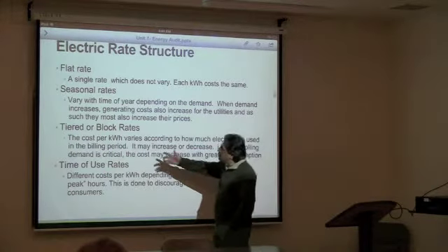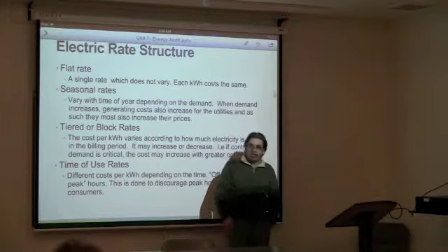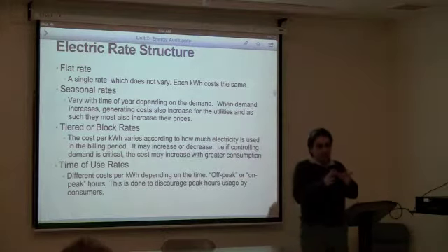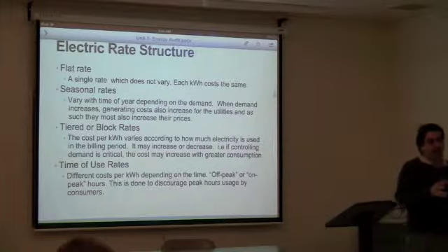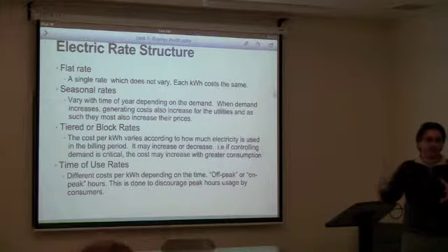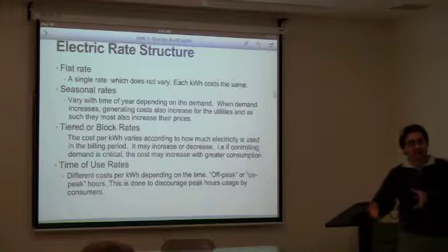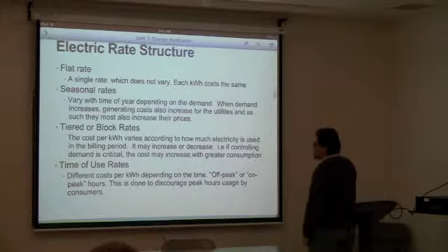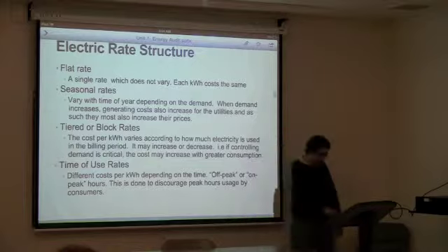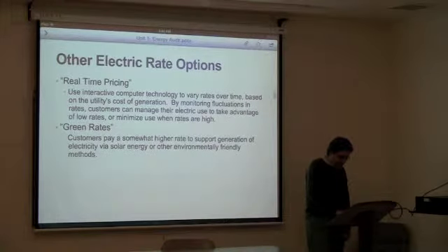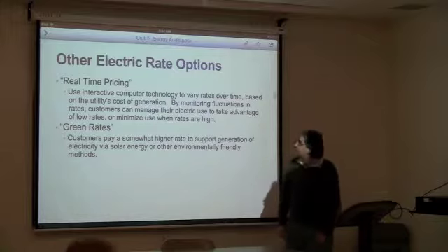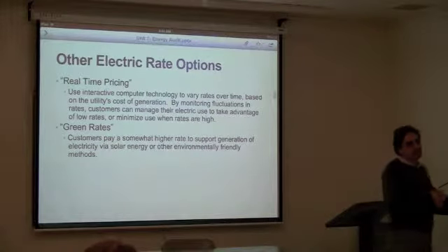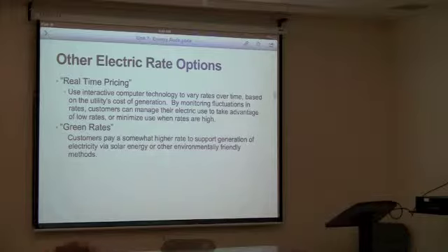Sometimes, most of the time for factories actually, they don't sell you electricity by kilowatt hour, they sell you a chunk of kilowatt hours. They say from the first kilowatt hour up to 100,000 kilowatt hours, this is the price. From 100,000 to 200,000, that's a different price, right? And so those are called block rates or tiers. And of course the time of use is important as well.